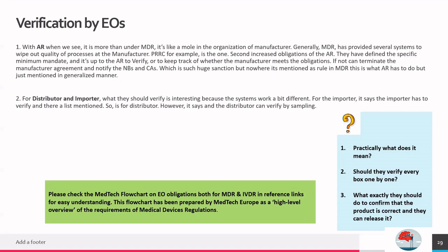What is the concept of verification? We have to know: a notified body verifies that the manufacturer produces devices by CE marked types, or by a CE marked quality system. That is also not done on a per product check basis, but they still verify it, because they have a process where the CE marking signifies that they're in compliance. So also in this case, you're not obliged to open every box, but rather, as an importer, have a procedure that ensures that the device that you import meets the criteria.